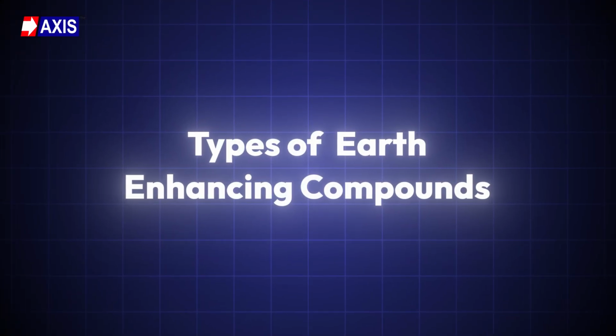It improves the soil condition around the electrode so your system meets the required resistance levels and maintains electrical safety. In simple words, it's a backfill compound made from a mix of minerals that has lower resistivity. Its main feature is the ability to absorb and hold moisture, which helps your earthing system maintain a consistent resistance over time. Now, let's understand the different types of earth enhancing compounds.